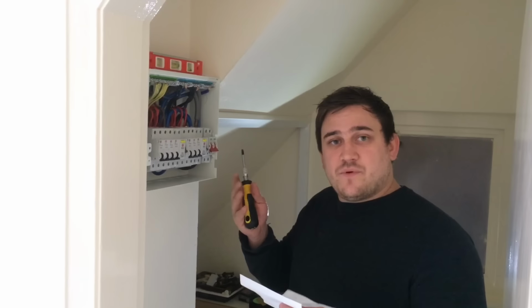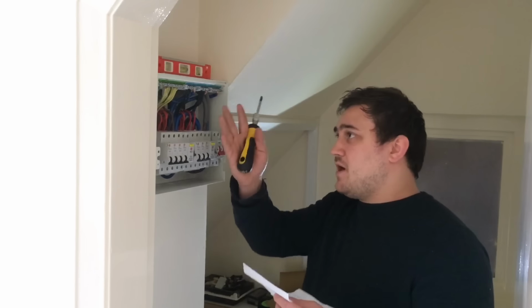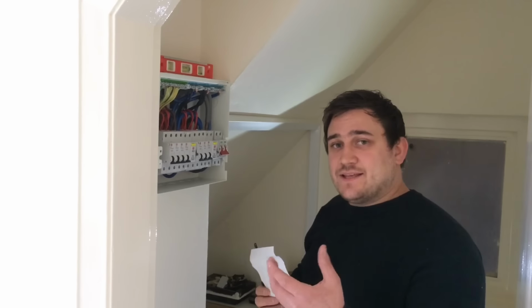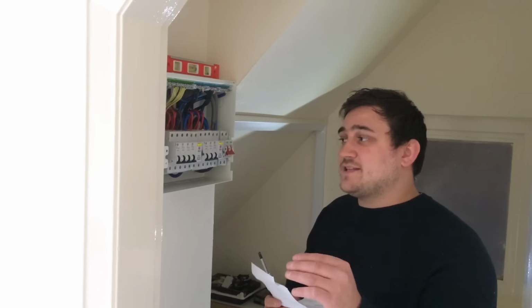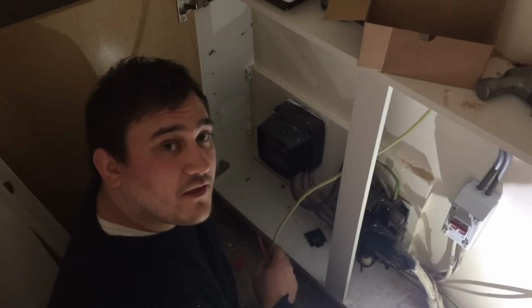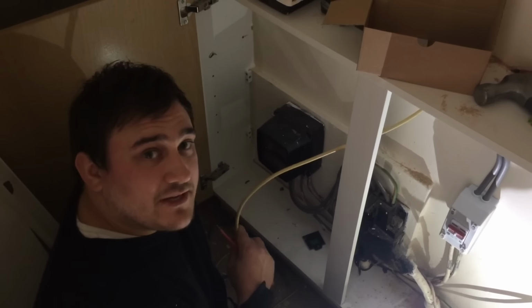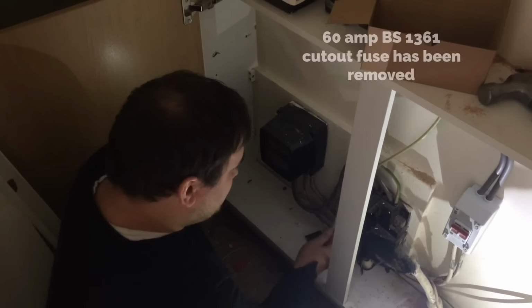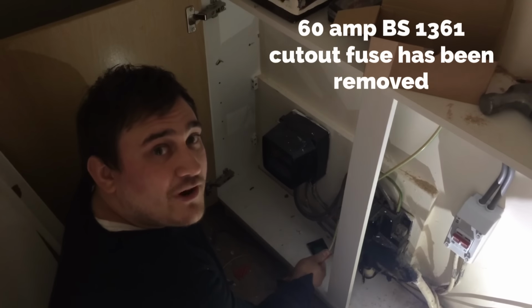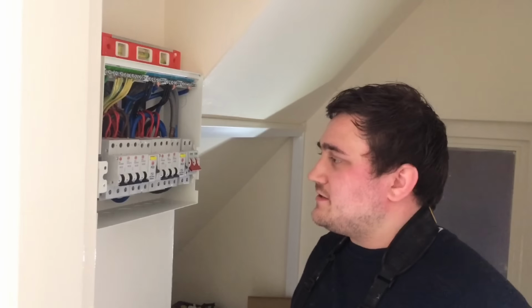That's that torqued up. Now we're ready to carry out the insulation resistance test. Even though I've torqued up all my breakers, main switch and my earth and neutral bars, once I've completed the insulation resistance test, I will then go around and just double check to make sure everything is torqued to the correct setting before we go live. I've just got to connect the 16mm squared earthing conductor to the supply authority's MET before I carry out my insulation resistance test. We've now moved on to our insulation resistance test.